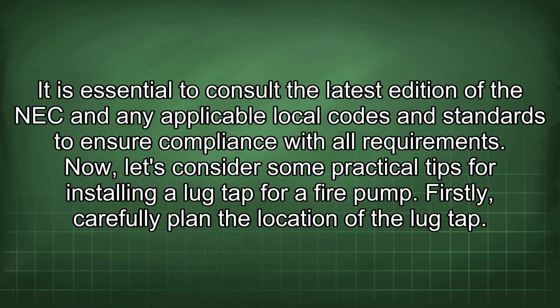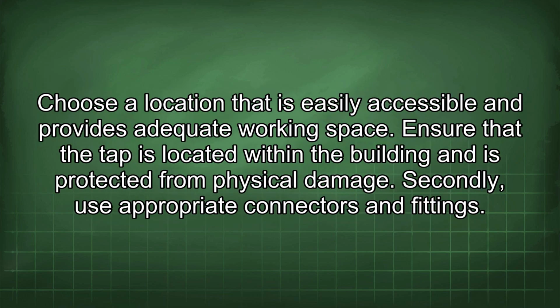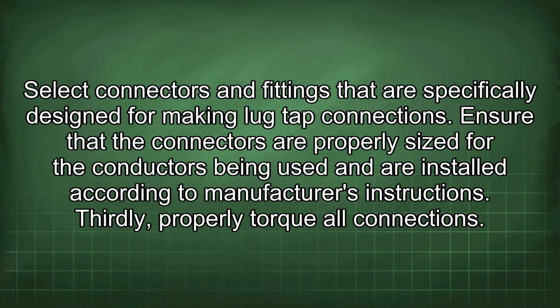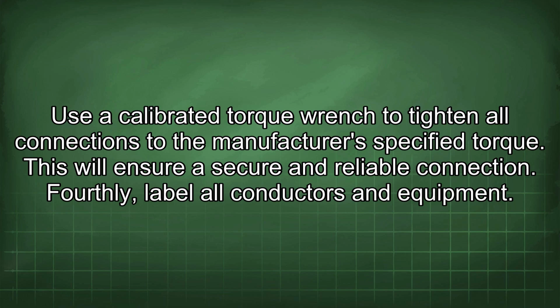Firstly, carefully plan the location of the lug tap. Choose a location that is easily accessible and provides adequate working space. Ensure that the tap is located within the building and is protected from physical damage. Secondly, use appropriate connectors and fittings. Select connectors and fittings that are specifically designed for making lug tap connections. Ensure that the connectors are properly sized for the conductors being used and are installed according to manufacturer's instructions. Thirdly, properly torque all connections. Use a calibrated torque wrench to tighten all connections to the manufacturer's specified torque.